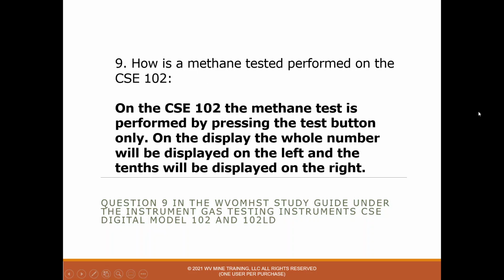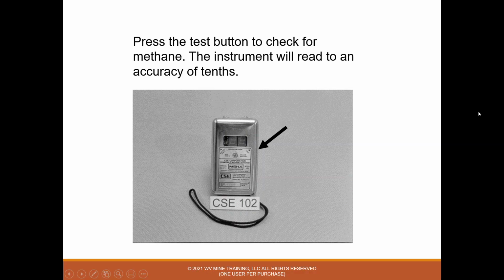Question 9, how is a methane test performed on the CSE 102? And the answer is on the CSE 102, the methane test is performed by pressing the test button only. On the display, the whole number will be displayed on the left, and the tenths will be displayed on the right. So this measures to an accuracy of tenths. So here's the picture again. Press the test button and check for methane. The instrument will read to the accuracy of tenths.